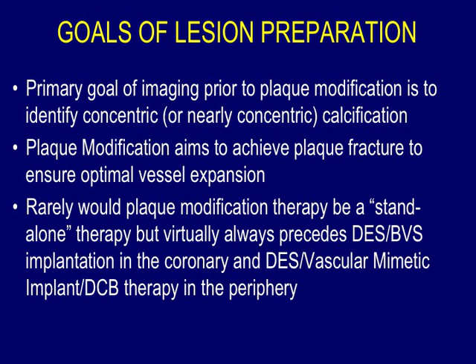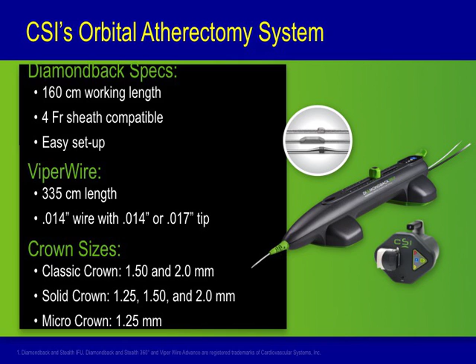I think here in the United States, what's available is the CSI Diamondback system, which is 160 centimeter working length and is 4 French sheath compatible. It runs over the Viper wire, which is 335 centimeters with either an 014 or an 014 with an 017 tip, and has 3 different crown morphologies. And the principle of this system is that it uses centrifugal force to, depending upon the rotational speed of the burr, develop an excursion about the midline that varies with the size of the burr and the speed.